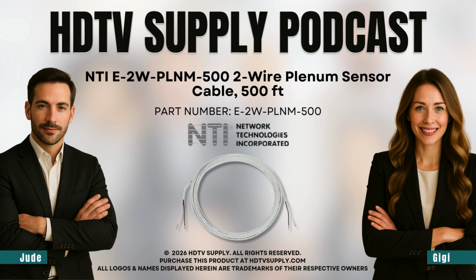Digging into the specs more, it's 22 AWG stranded bare copper. 22 gauge is the sweet spot for these low-voltage jobs. It's thick enough to carry a signal reliably over a good distance, but still flexible enough to snake through a tight ceiling grid. And stranded means it's less likely to break when you bend it, much less likely than a solid core wire. You can pull it around a sharp corner without worrying about the connection failing.